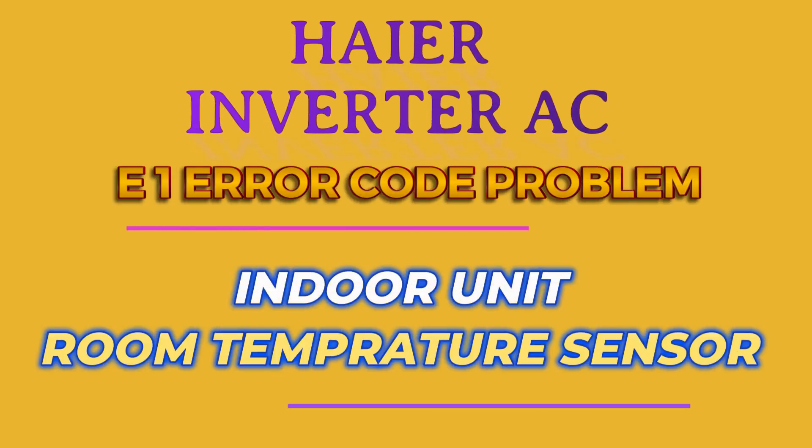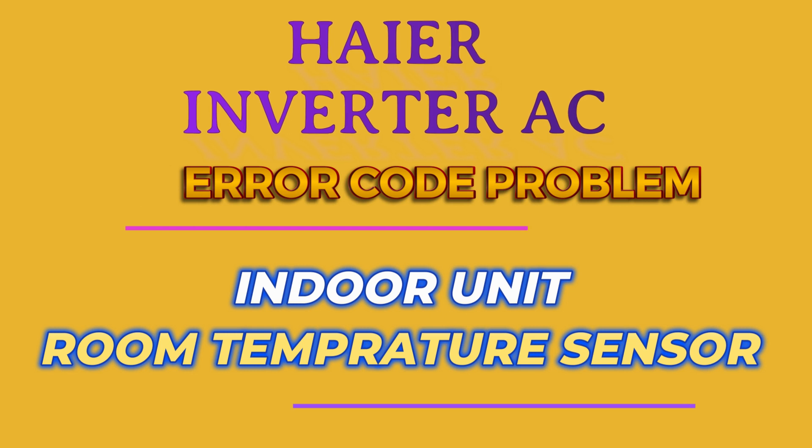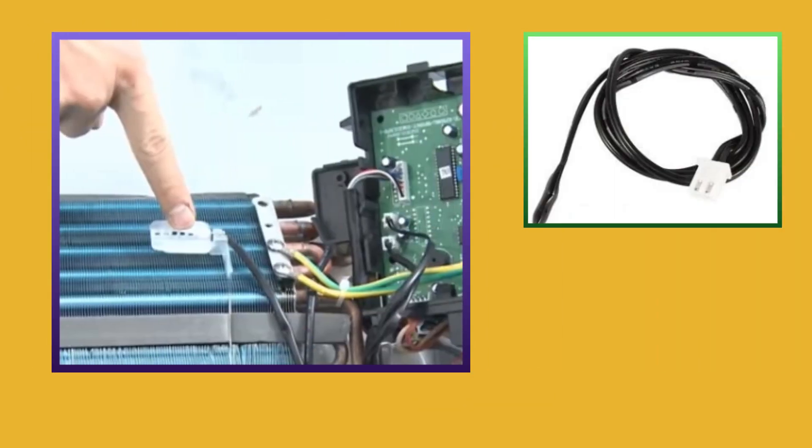If E1 error is coming in Haier AC, then it is the error of indoor unit room temperature sensor. This sensor is installed in the coil of the indoor unit. This error can occur in your AC due to three reasons.